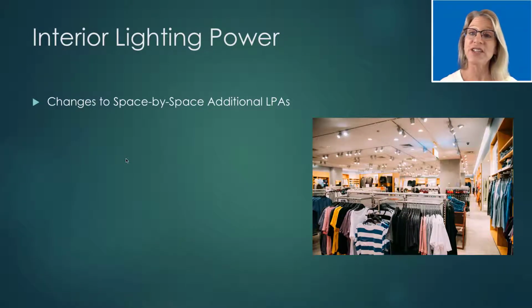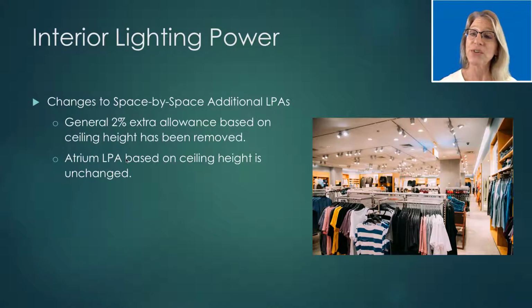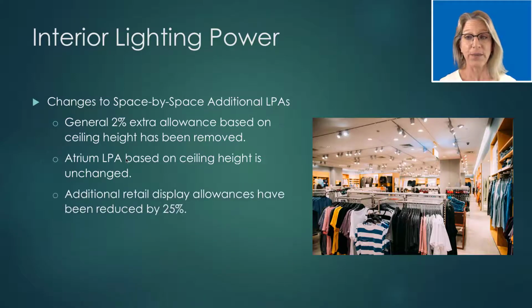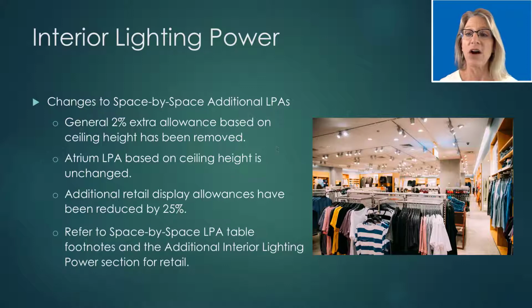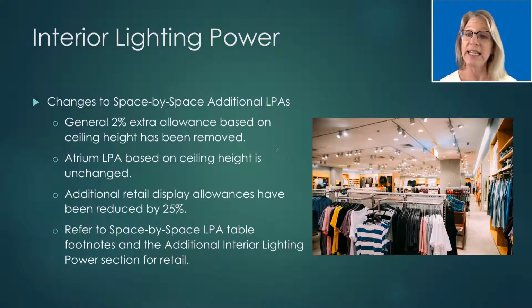There are also several changes to the additional lighting power allowances. The general 2% allowance based on ceiling height is no longer available. In the 2015 WSEC, this applied to spaces with ceiling heights greater than 20 feet, and in office and library areas with ceiling heights greater than 9 feet. Now, note that the atrium LPAs that are based on ceiling height are unchanged. The additional retail display allowances have been reduced by approximately 25%. And all of the additional allowance information is located in the footnotes for the space-by-space LPA table, and then under the additional interior lighting power section for retail.